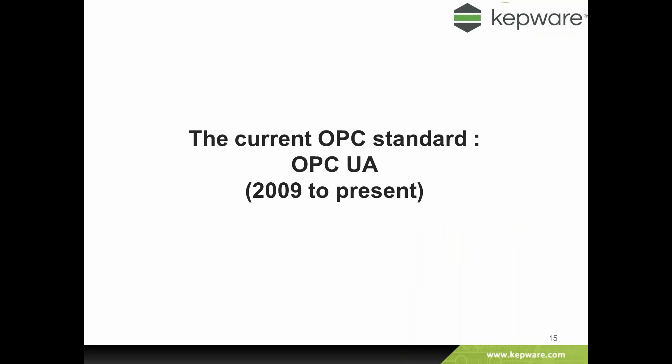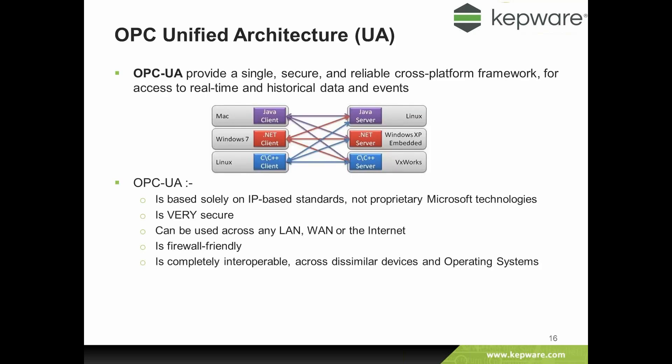The current OPC standard is OPC UA, which was launched in 2009 and is still the present standard. It is a completely different model from OPC DA. It's based upon normal rules of networking — connections are between IP addresses, not based upon Microsoft proprietary technologies. It's very secure, can be used between any two PCs with IP addresses across any type of LAN or WAN, or even across the internet. It's very firewall-friendly and can run on different operating systems such as Apple Macs or Linux, making it far more flexible and suited to today's requirements.